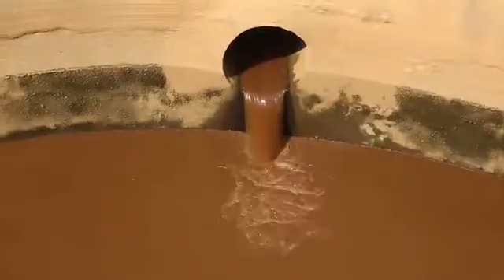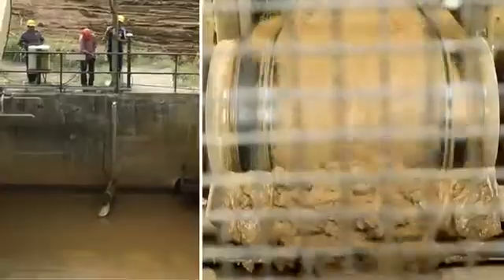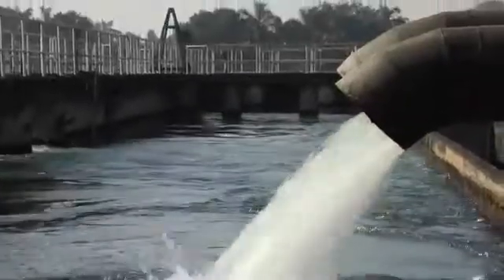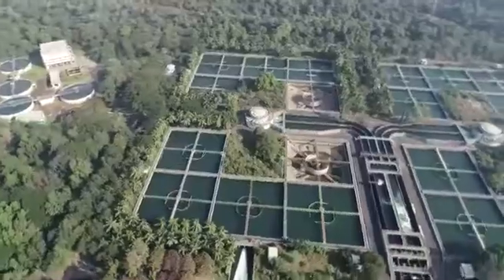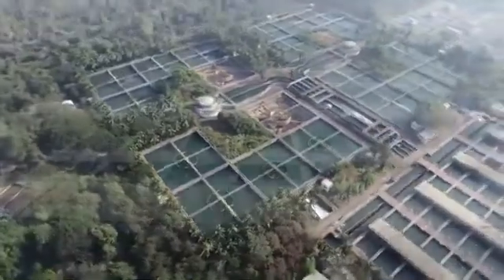The sludge water generated in the pre-treaters is conveyed to a sludge recovery area plant where sludge is segregated in the form of sludge cakes and supernatant water flows back to the inlet bay. The filtered backwash water is also recirculated into the inlet bay. Thus, the objective of zero waste water discharge from the water treatment plant is achieved.